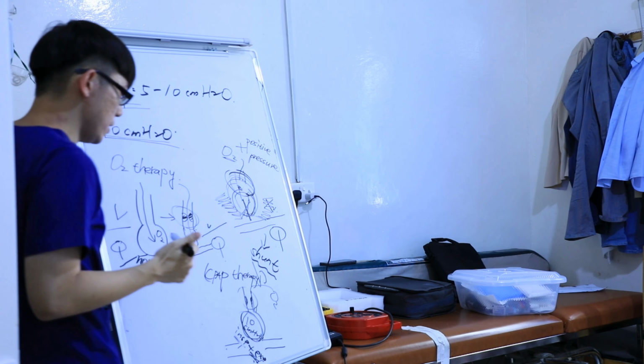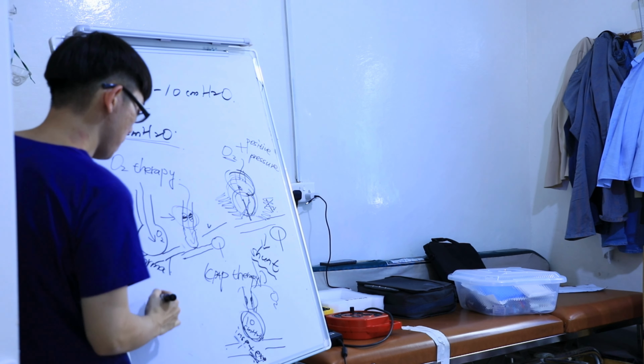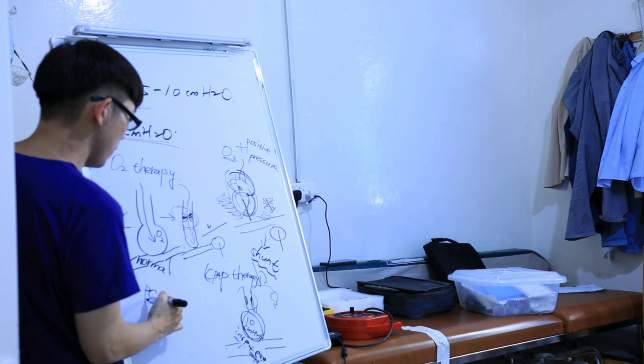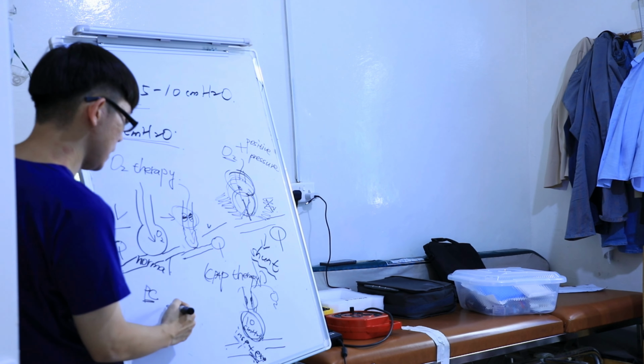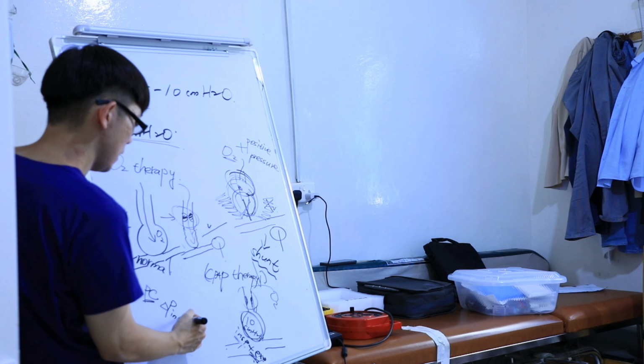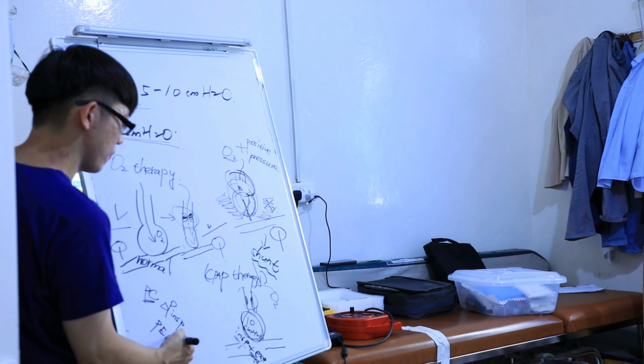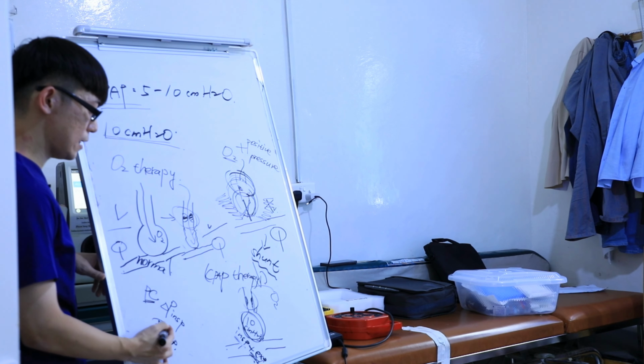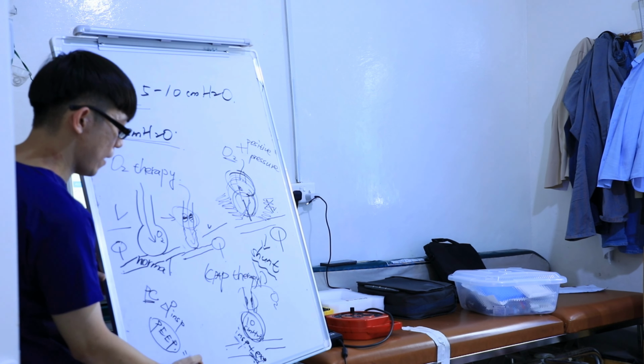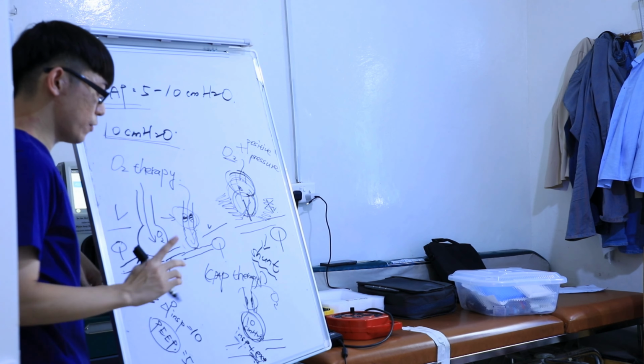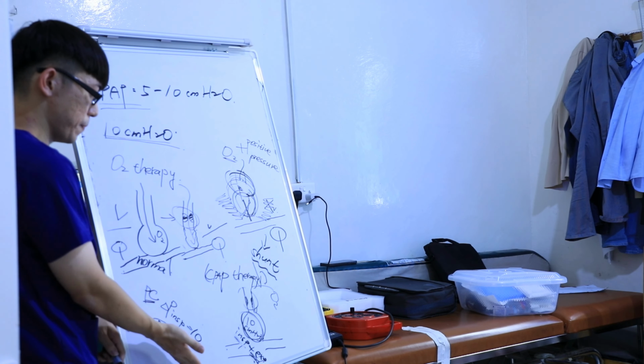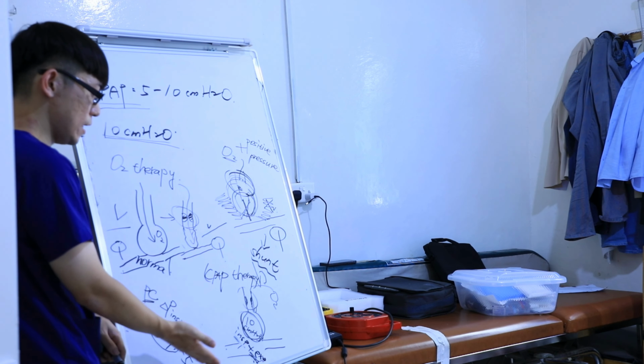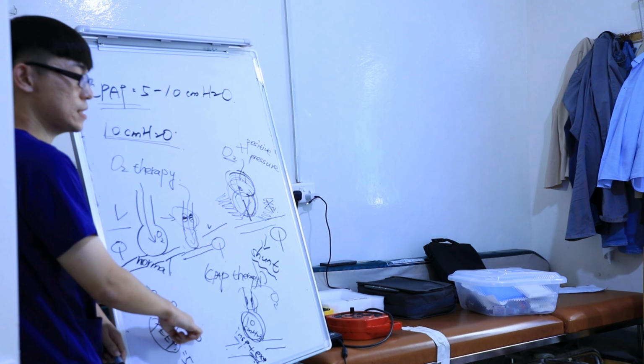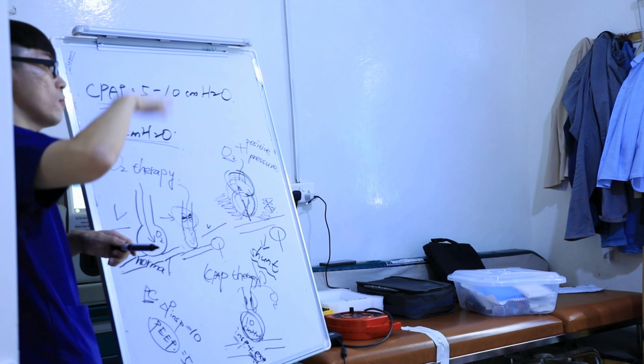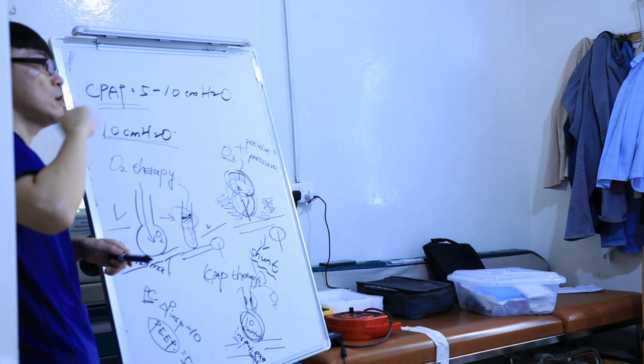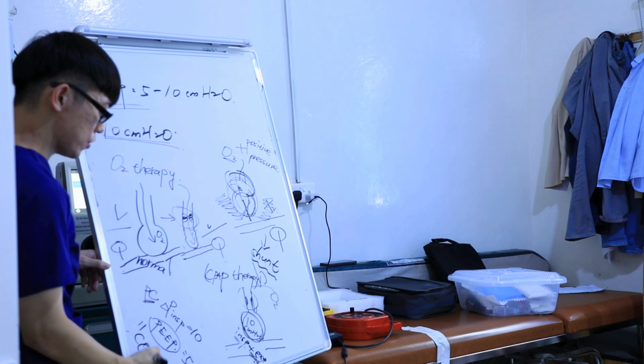If we want ventilation, like yesterday we talked about maybe pressure control, PC mode, we require two settings. The first is the inspiratory pressure. Second is the PEEP value, right? So during expiratory phase is this PEEP value. Maybe we set 5. Inspiratory pressure maybe 10. So during expiratory phase is 5 centimeter water, and during inspiratory phase is 5 plus 10. So the change of high pressure and low pressure means that the patient has ventilation, okay, to wash out carbon dioxide, to wash out CO2.